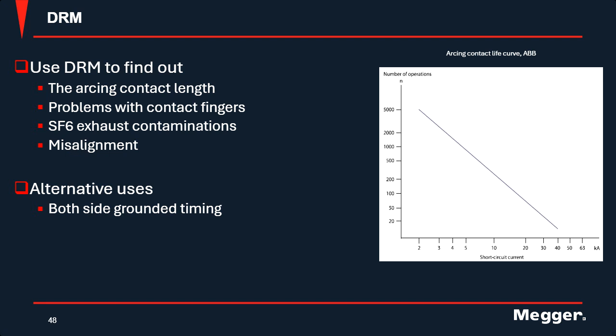Again, both sides of this can be grounded. You can do timing with this, but as I said, it won't look like conventional timing. It is more of a resistive curve where you would have to know the resistance of your ground loop versus the resistance of your contact, and you have to put the threshold between those two. So it's not as straightforward as the traditional timing or the DCM, the dynamic capacitive measurement.